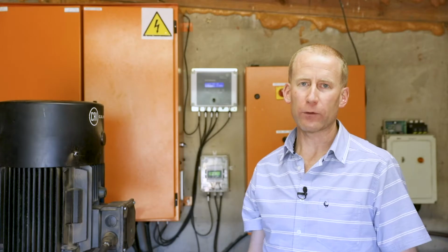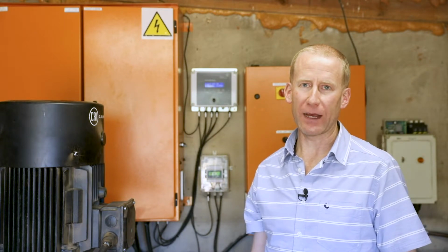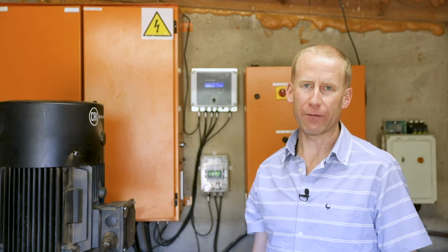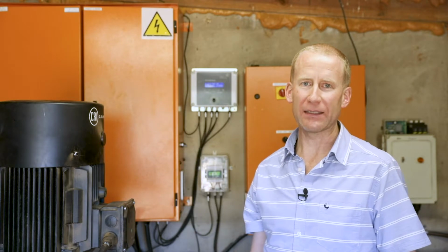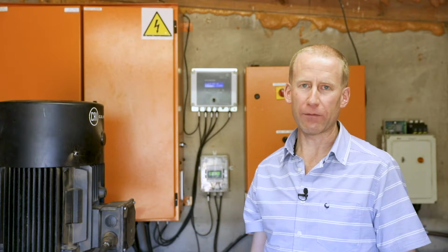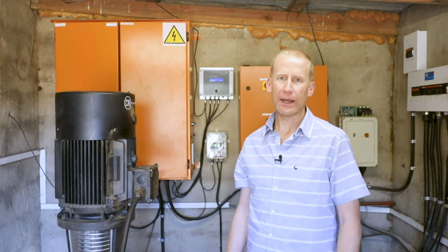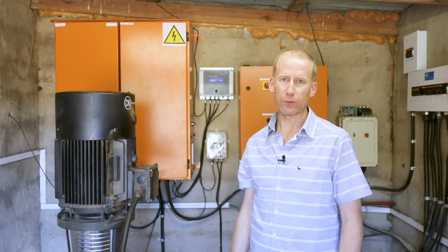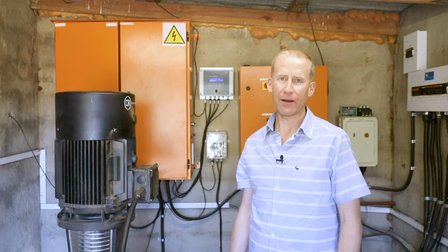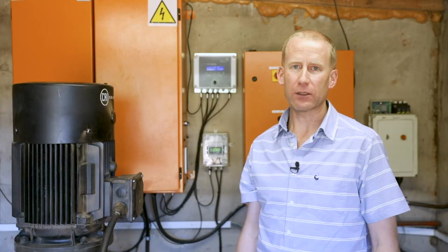For example, if there are 2 pumps, each drawing 55 kVA installed on a 100 kVA transformer, then it means that you can only run 1 pump at a time. This results in 45 kVA of unutilized capacity on the transformer. If in our example, each pump delivers 200 cubes of water per hour, then in a day, the system can only deliver 4,800 cubes of water.